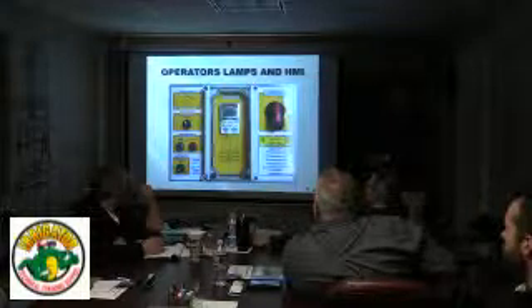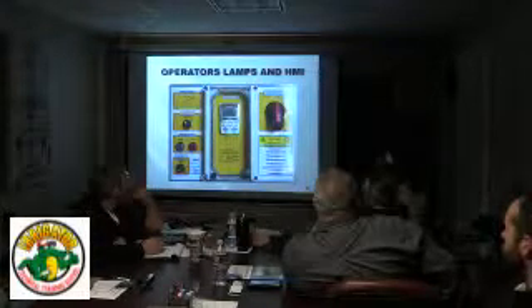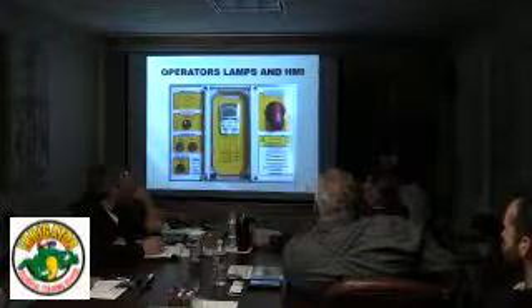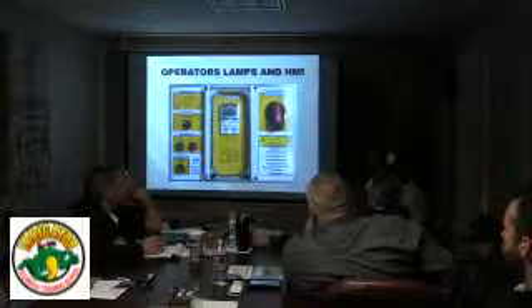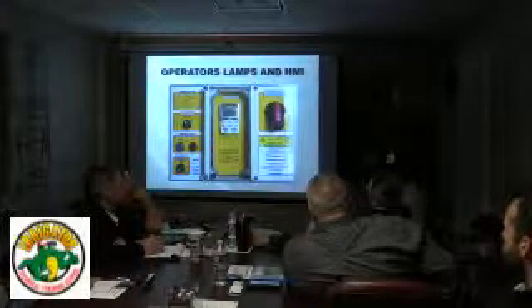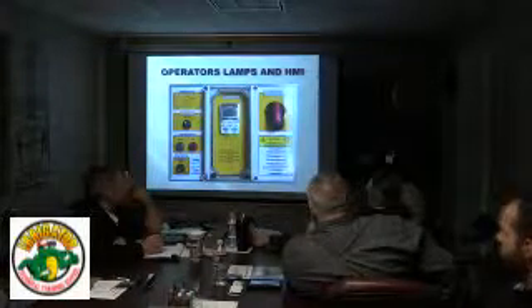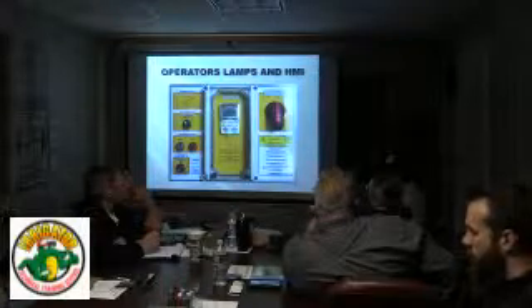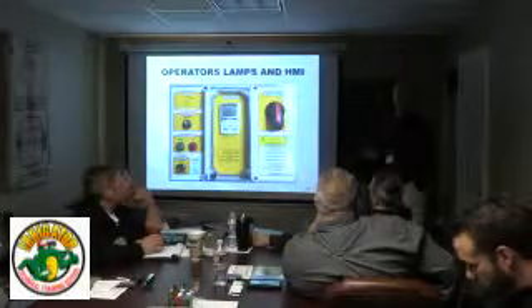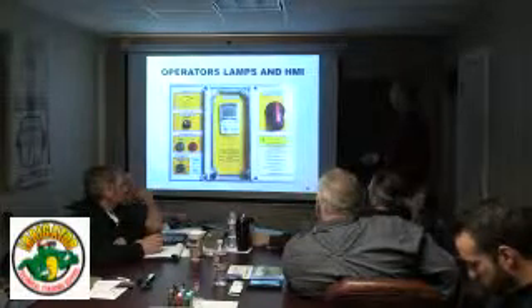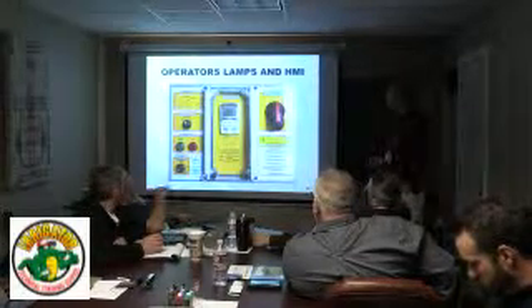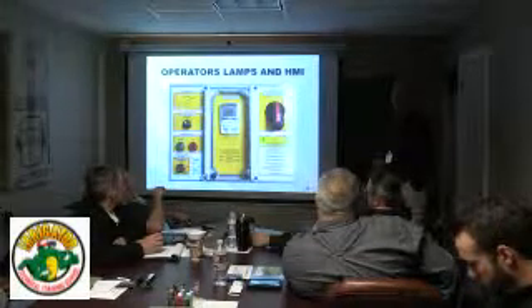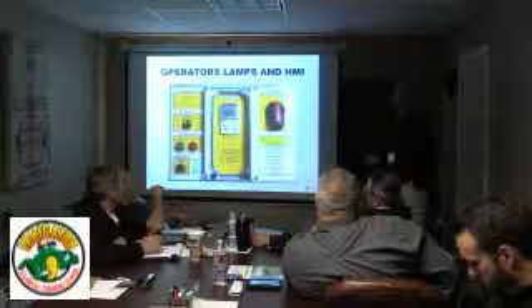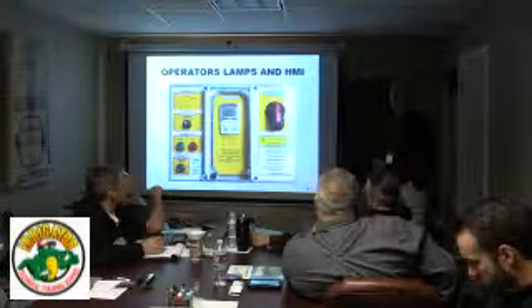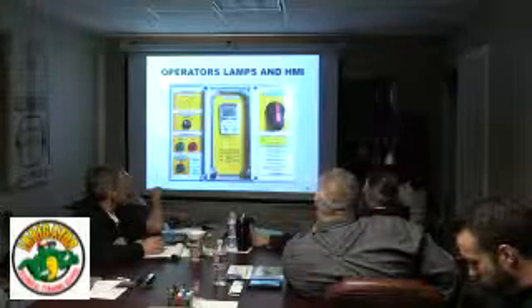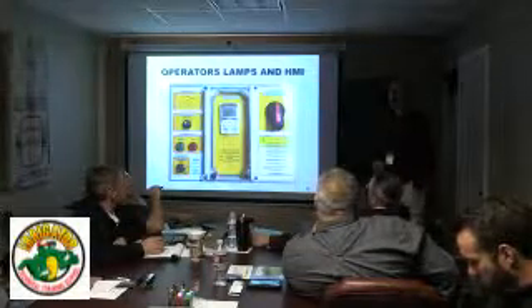Another thing to keep in mind is that when you switch to hand mode on almost all of our panels, especially our pump stations, the hand mode is mostly for testing, and so it overrides all the safety functions. If that system has a high pressure switch on it or a low flow switch on it, it's not going to fault out when you're in the hand mode. Once you go to hand mode, the drive then looks at this manual speed control. So you just dial it up or down, and it follows that speed. But be aware it's not going to shut down on high pressure. If you crank that all the way up, depending on the pump or the system, you could get 150 PSI within a few seconds.